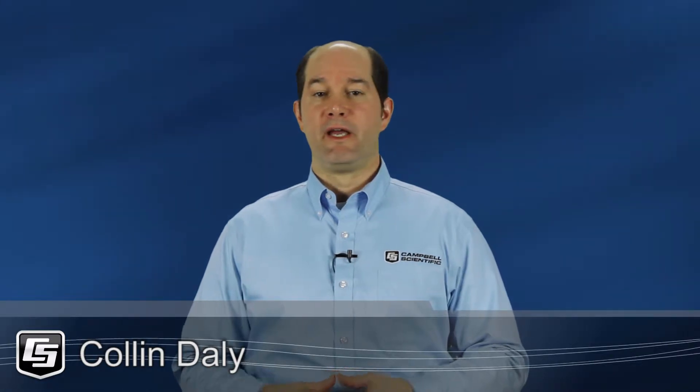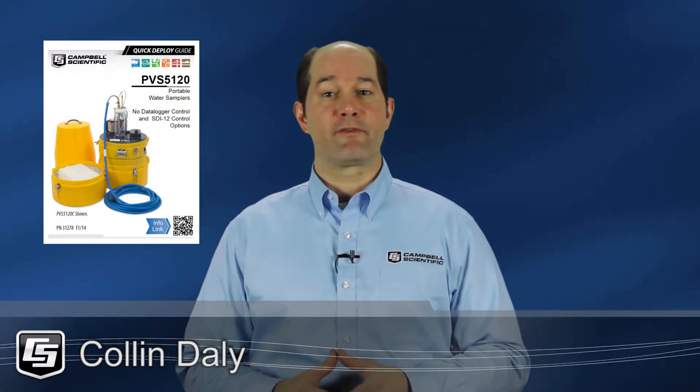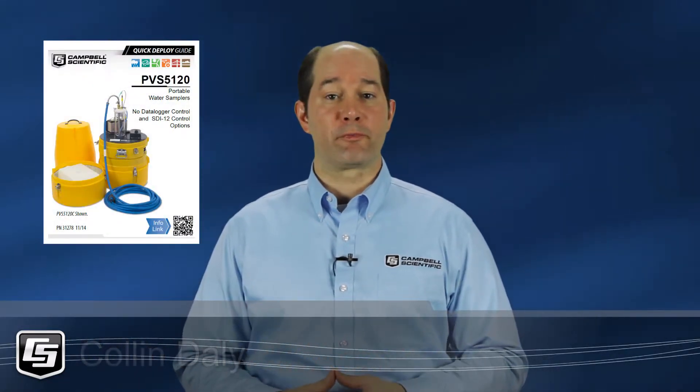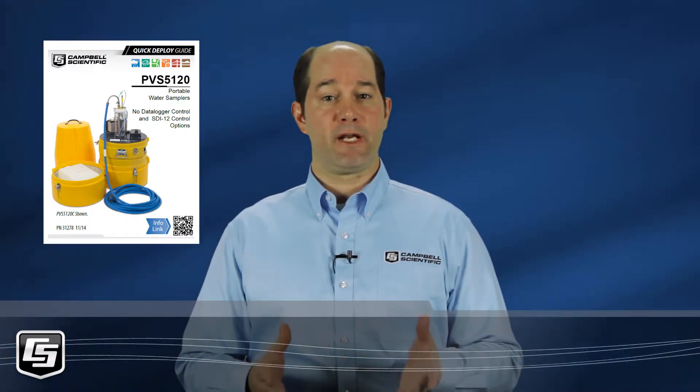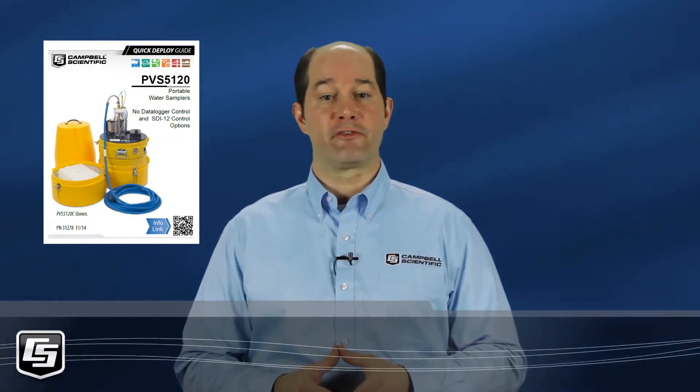Hello, I'm Colin Daly of Campbell Scientific in Logan, Utah. In a different video, Barb Utley, one of our water quality experts, walked us through setting up SDI-12 control of the VSC-100 to allow a data logger to communicate with and control a 5000 series sampler. Today, we'll be setting up that data logger, a CR1000.